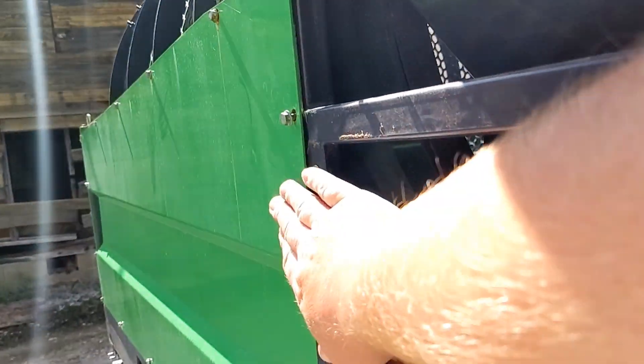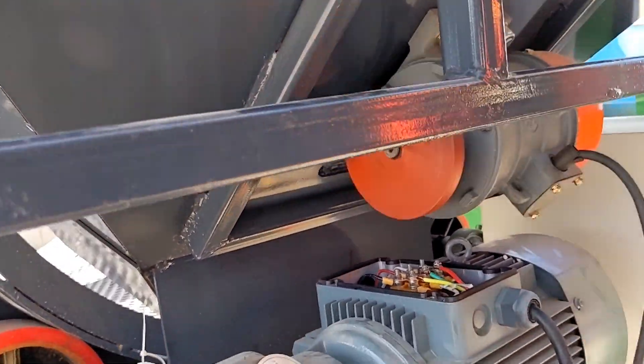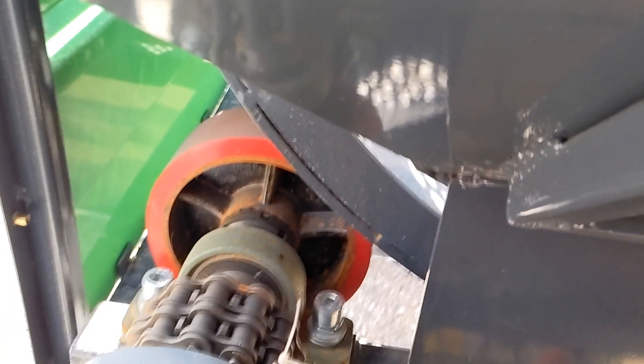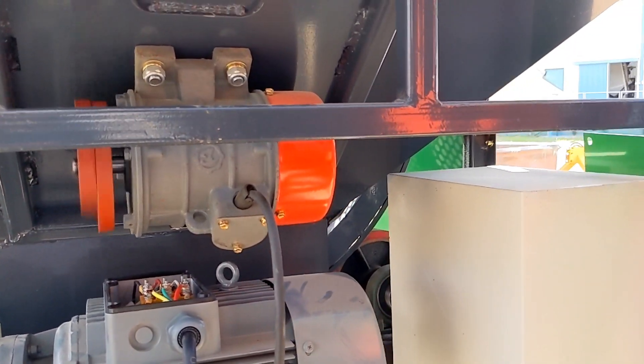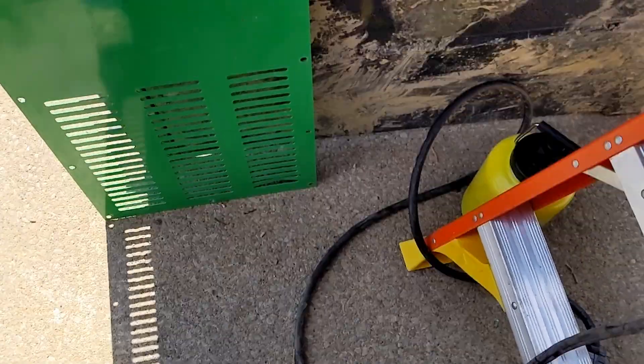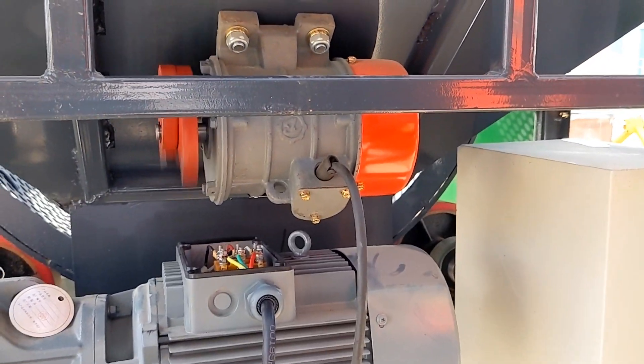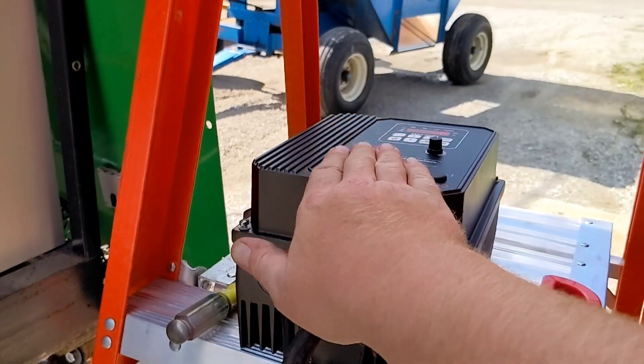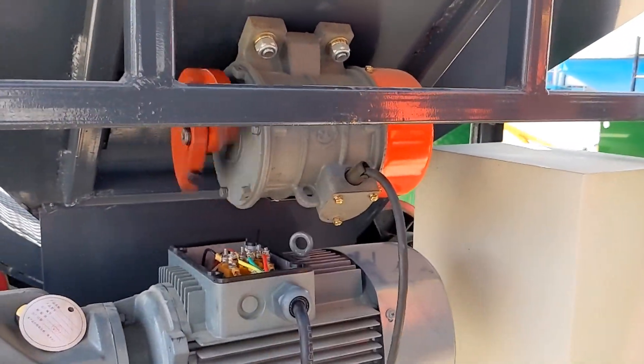We're going to speed this up to 600 and see what happens. You can see this loose panel — it's definitely got vibration. I don't know if that's coming through on camera, but it's vibrating. I can actually feel the concrete vibrating down here, so that's kind of crazy. Definitely would be wanting to run this at about half the RPM that one of these could produce.